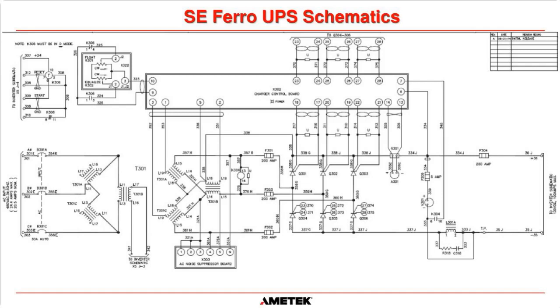Okay. We have our voltmeter here. The voltmeter is protected by a small fuse, just in case there's a fault in that meter. It doesn't put a short on the output of the system. The fuse will blow and the system will continue to operate as normal.